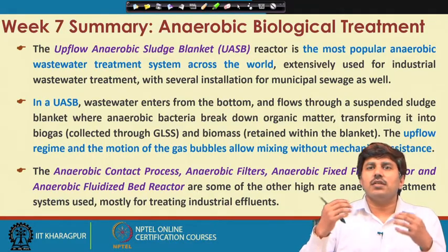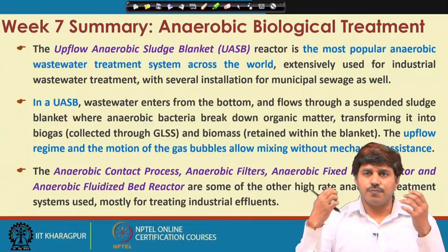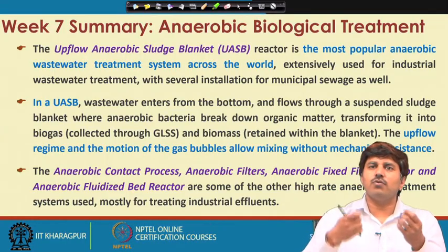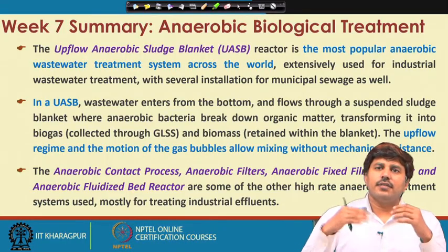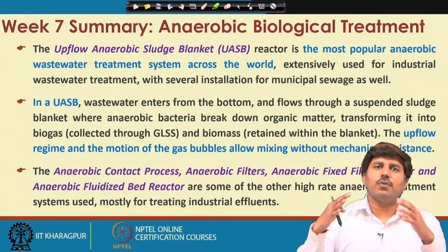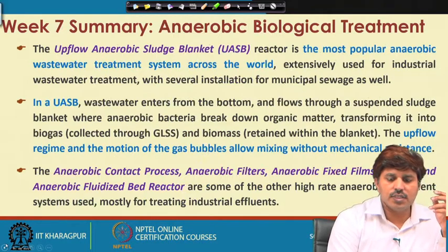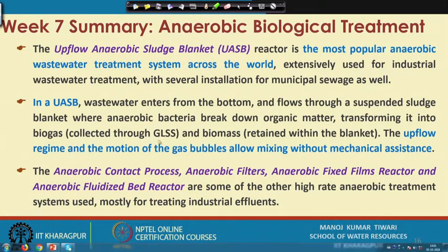But due to this, when the gas or water moves up, some biomass also moves up, so we provide a settling zone where this biomass gets settled, and on top of that there is a GLSS, the gas liquid solid separator, which is responsible for the separation of all these elements.